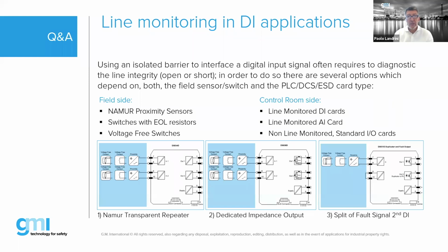When you are using an isolated barrier to interface a digital input, you're basically interposing an isolation between the input and the output. So you're not seeing exactly the field, you're seeing a replication of the field switch. So field opened, you see an open contact. The field closed, you see a closed contact. But this implies that you might not be able to do line monitoring to verify if the line is cut or shorted. So there are different solutions to this application.